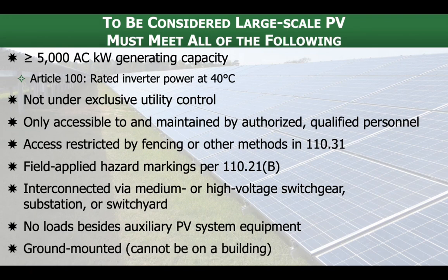And then finally, these have to be ground mounted. Cannot be on a building. Now, you can put a 5 megawatt AC system on a building. You need a pretty big building. You can certainly do that. You can put bigger ones on. There are, absolutely. But the allowances that we'll see in Article 691 for large-scale PV cannot apply. This has to be on the ground. It's going to be fenced off. Only people that know what they're doing are going to be getting in there. This is basically a system that is built and operated to make electricity. There's investors, there's loans to repay, there's financing going on, and it's not there to serve a building or a house specifically.